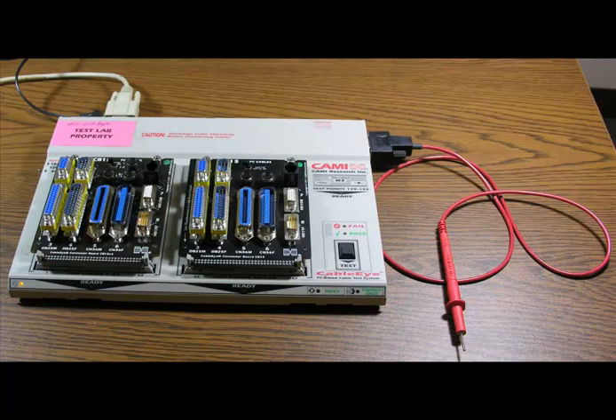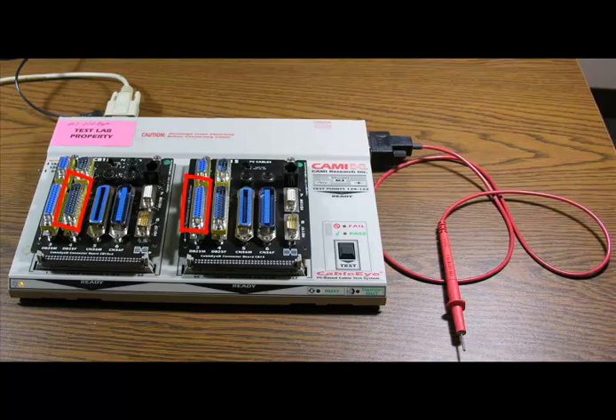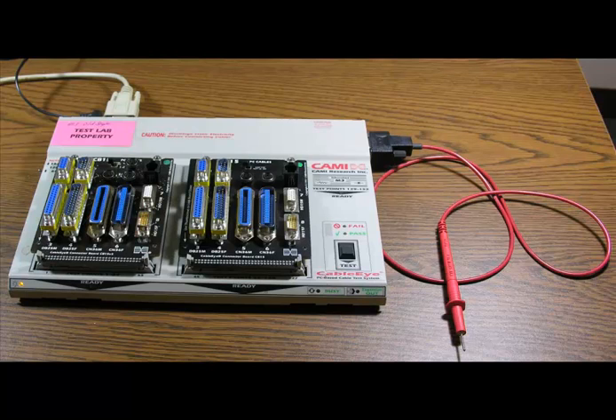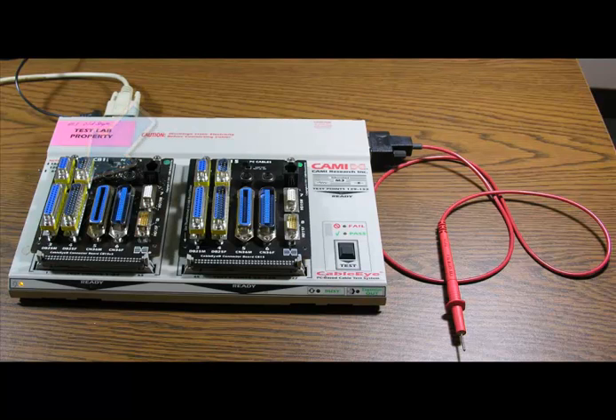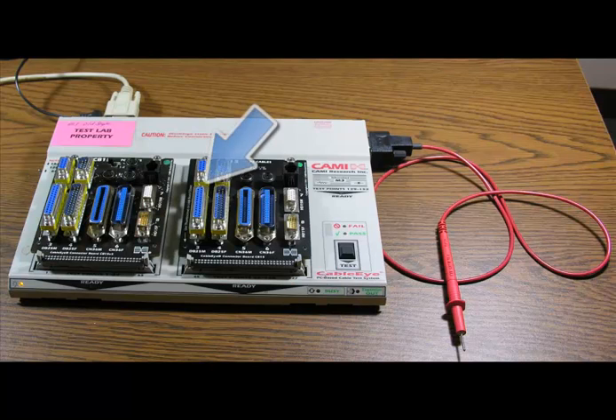First, attach your mating connector boards to the tester exactly in the positions in which they will be used. For the purposes of this demonstration, we'll be using two standard CB15 boards and mapping only the DB25 female on the left and the DB25 male on the right. Note that we're mapping the mating connectors. So, for the DB25 female, we're mapping the DB25 male on the left and for the DB25 male, we're mapping the female connector on the right.